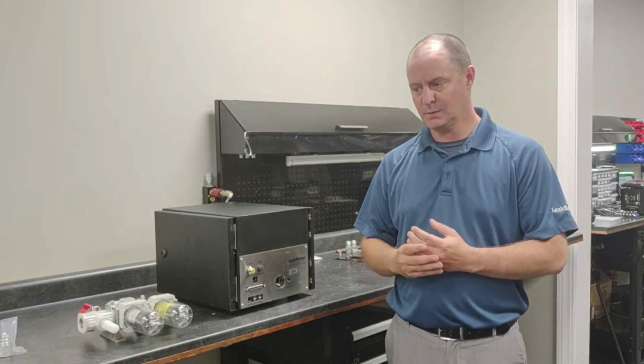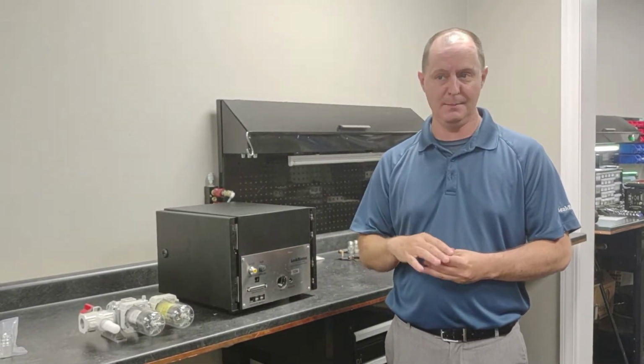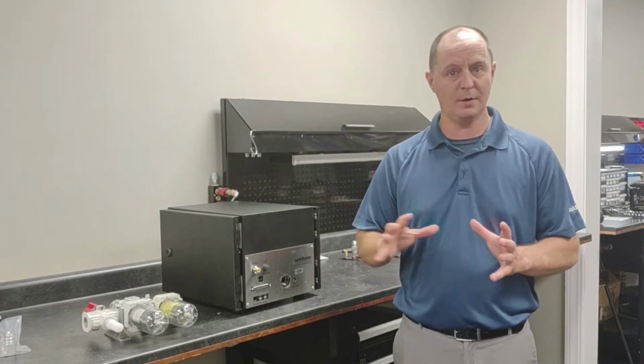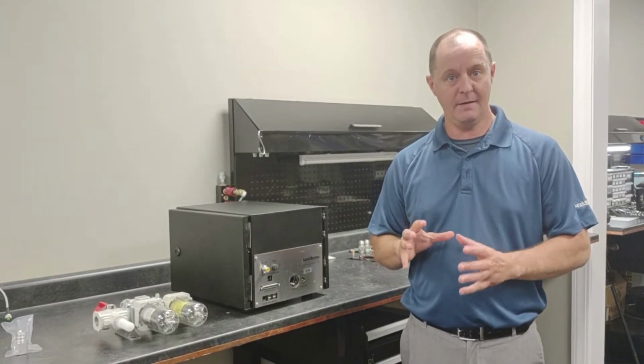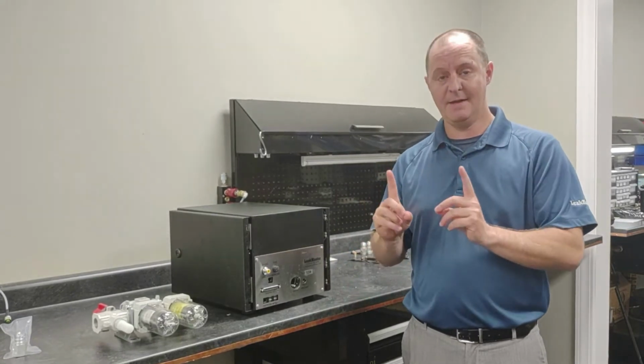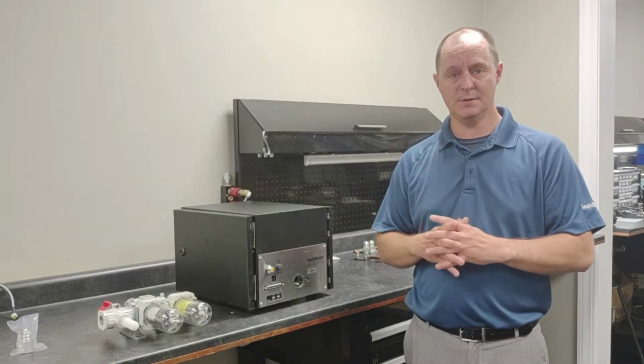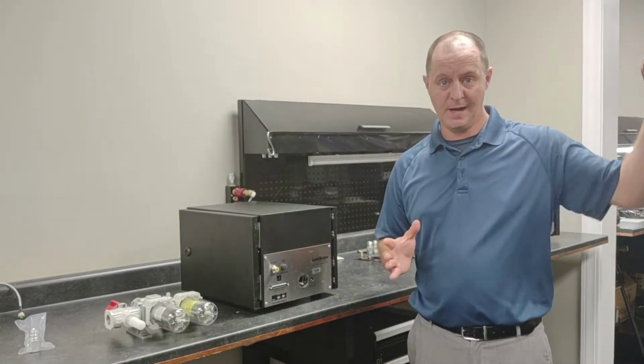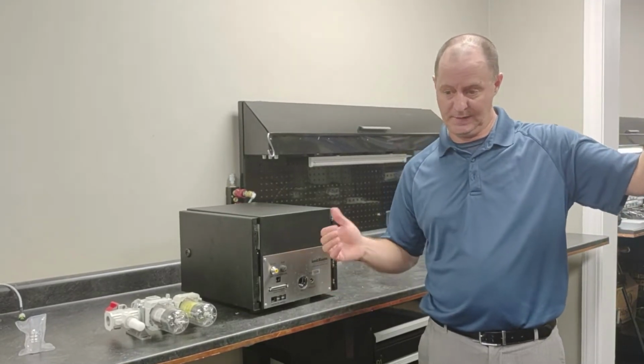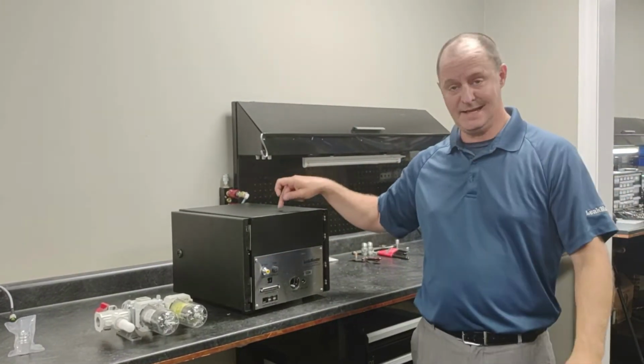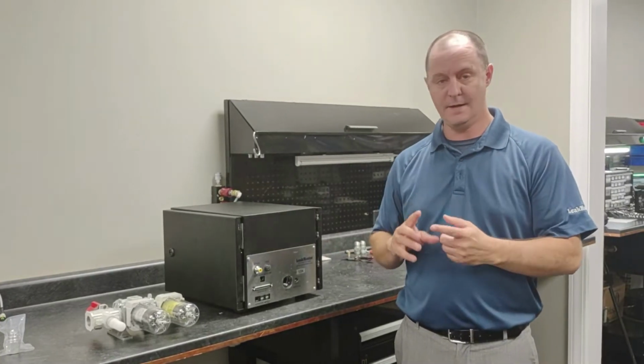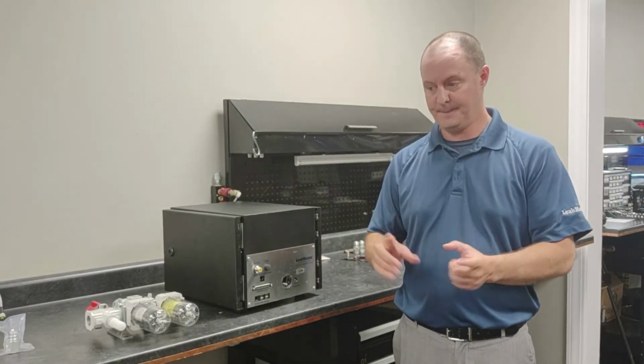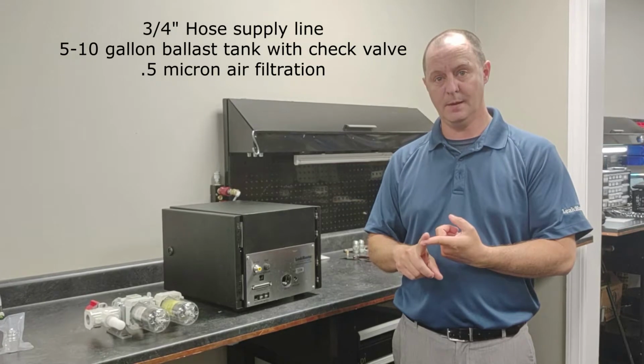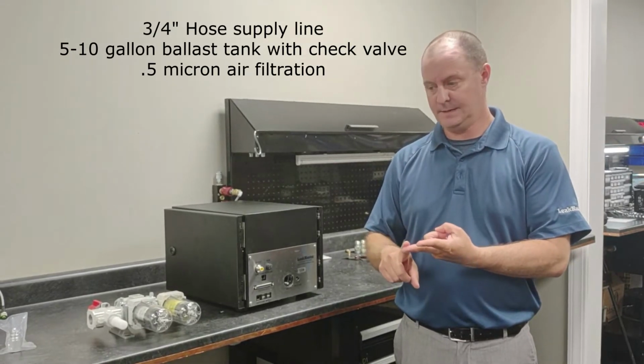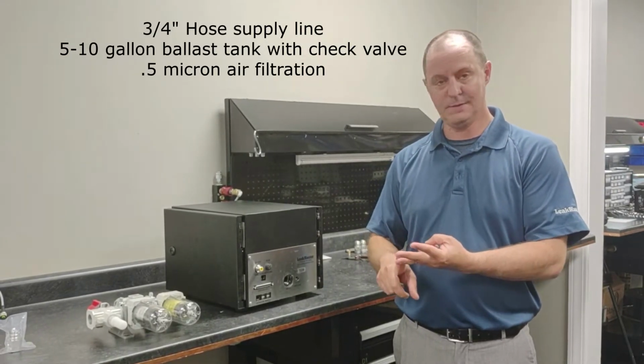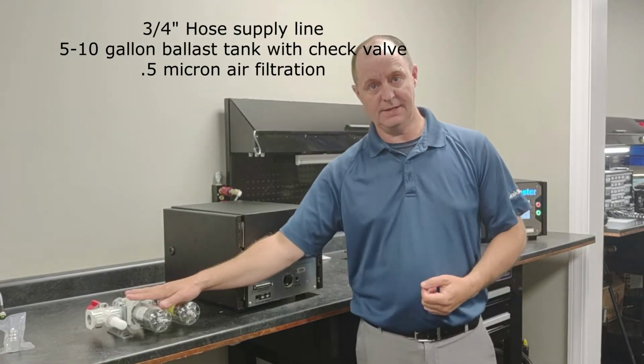We also recommend a check valve on the input of the ballast tank, so no other equipment can rob air from our station, which can have effects on your leak test results. If another station close by is consuming a lot of air and it pulls air in the negative direction from here, you can see negative flow rates. So it's very imperative to ensure that you have large enough air supply lines, a check valve on the input of a properly sized ballast tank, and good clean dry air.